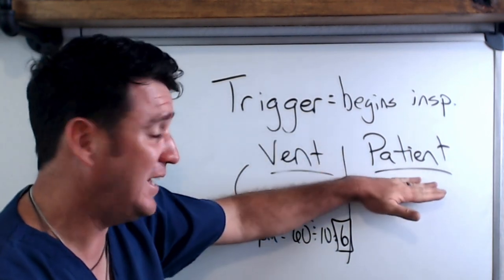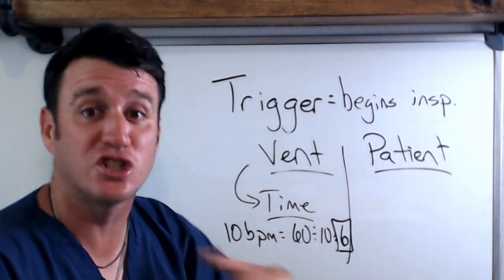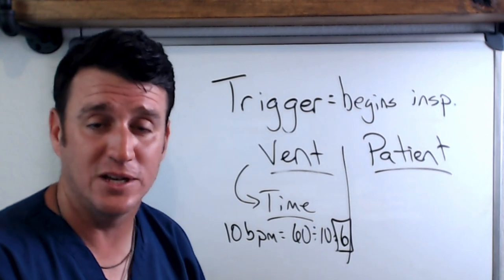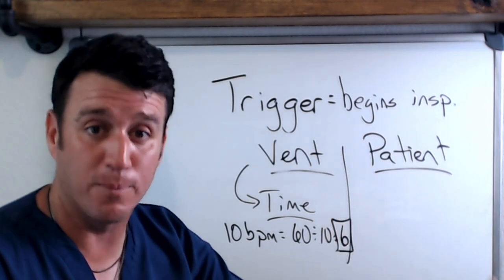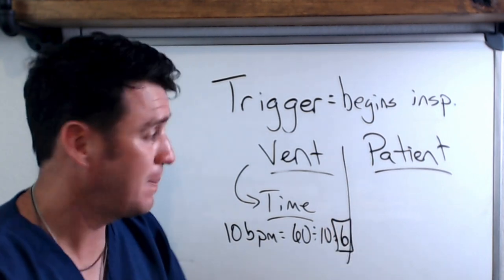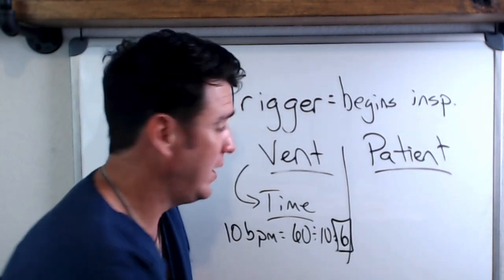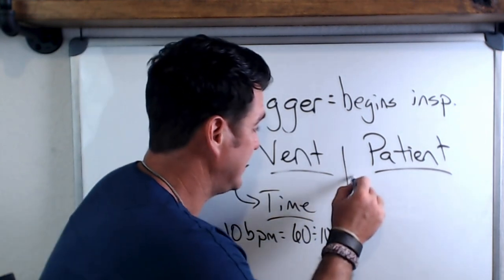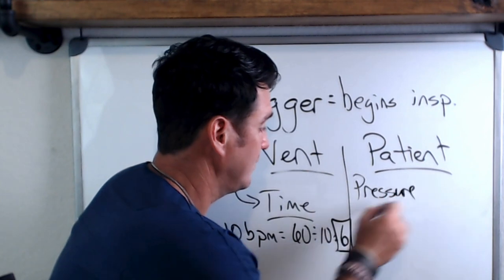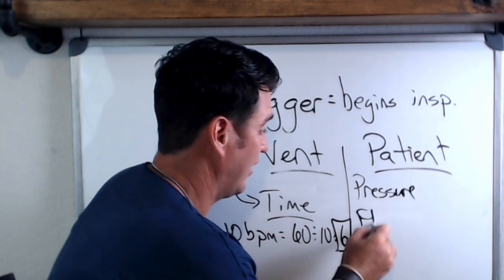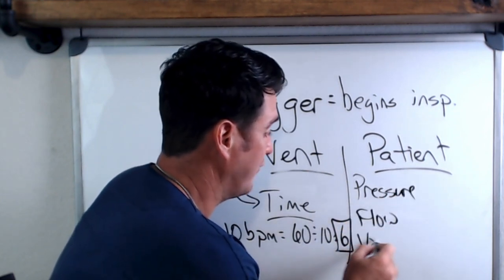The patient can also, in certain modes, initiate or trigger a breath. This happens in one of three ways: either pressure, flow, or volume.